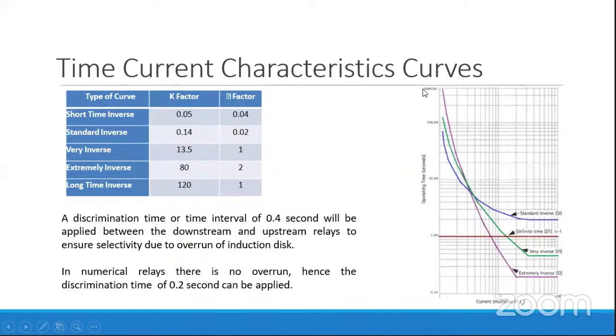For certain curves, you can see here on the right hand side figure, for this particular curve how much time the relay will take when it is at TMS 1. For every curve it is plotted how much time it will take to operate if TMS is 1 and for a particular current value. With this we can determine the time of operation with the help of these parameters, K and alpha, which are given for different types of curve.